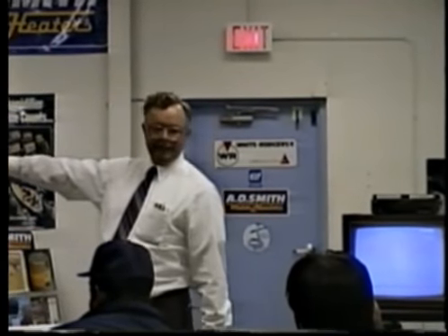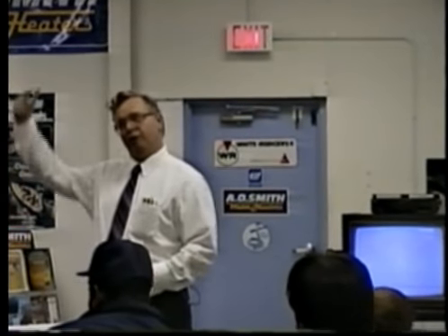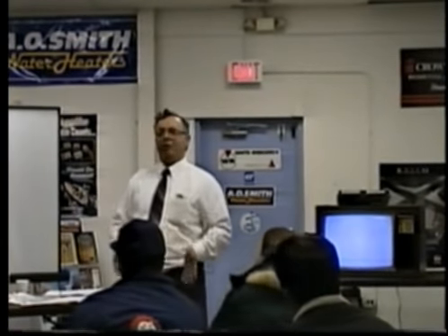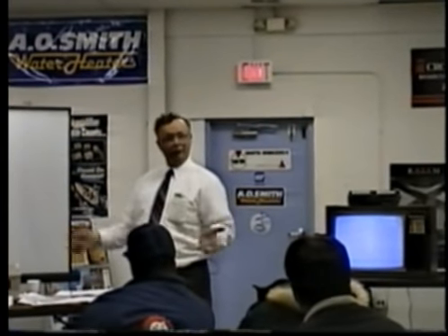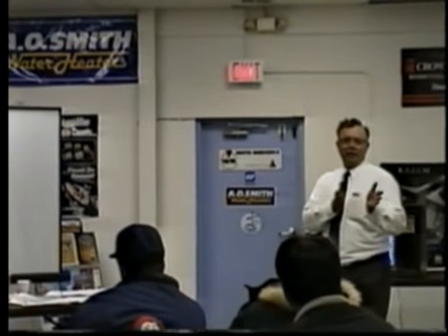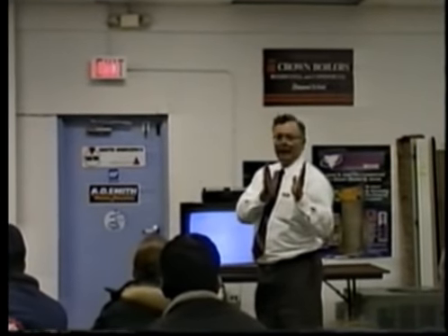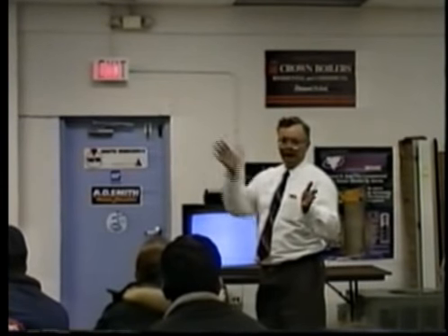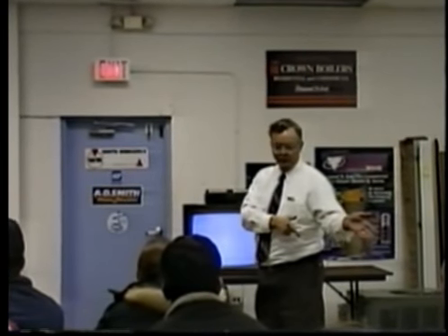But what goes down the drain on a condensing furnace? Water. And on a 20 below zero day, the furnace is running all the time, it's the same question. Gee, how many pints of water go down your drain in a 24-hour period? I don't know, because it's gallons. It's the same thing. Products of combustion, ladies and gentlemen, is CO2 and H2O.